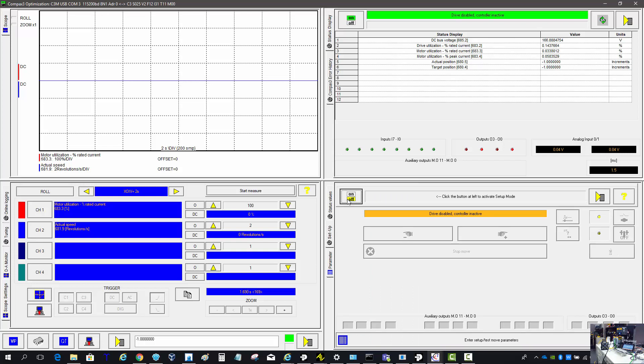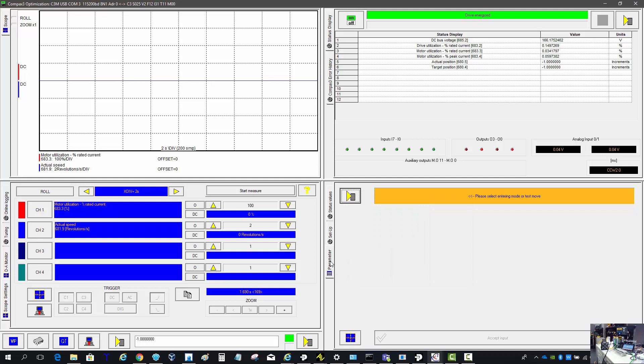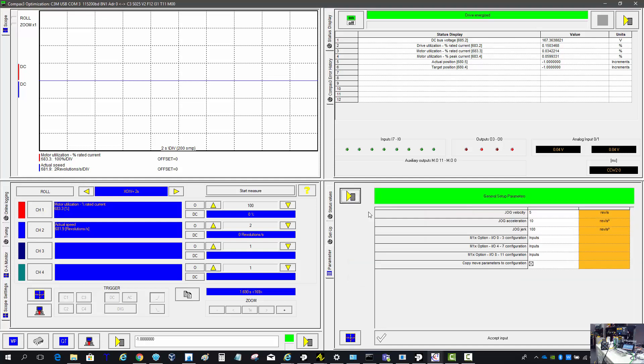If you go into the setup tab, you can actually grab control. This kicks the pack offline and you're grabbing control from your PC locally. You can energize here, which will disable the brake. You can also manually disable the brake if there's a brake on the motor. You can jog it from here. If you click into the setup test move parameters — also accessible from the parameter tab — go into the general setup tabs to find your jog velocity. This is set by default based on the drive configuration. There's also a relative test move option which just runs continuously in the same speed and direction.